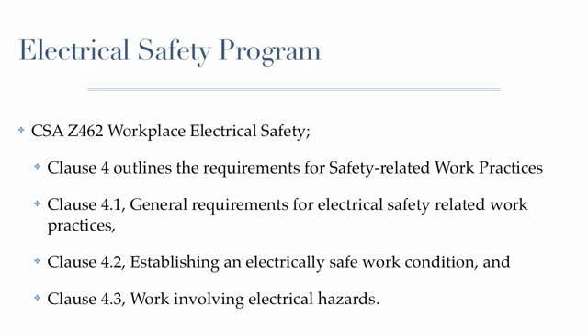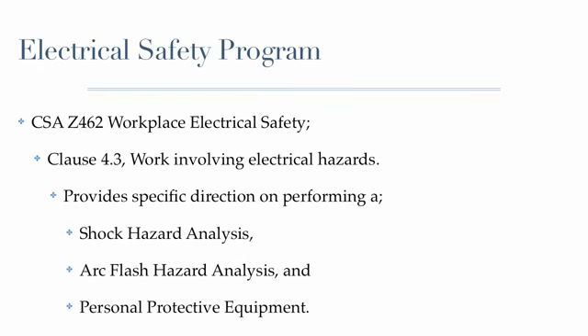The CSA Z462 Workplace Electrical Safety, Clause 4, outlines the requirements for safety-related work practices. Clause 4.1 outlines the general requirements. Clause 4.2, establishing an electrically safe work condition, and Clause 4.3, work involving electrical hazards. Clause 4.3 provides specific direction on performing a shock hazard analysis, an arc flash hazard analysis, and personal protective equipment.